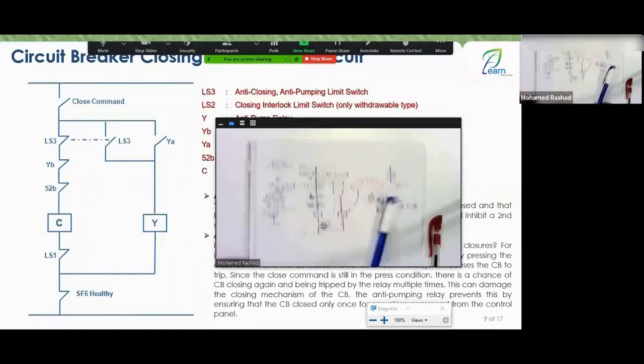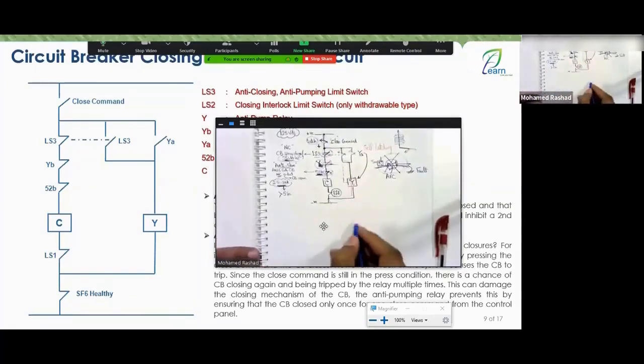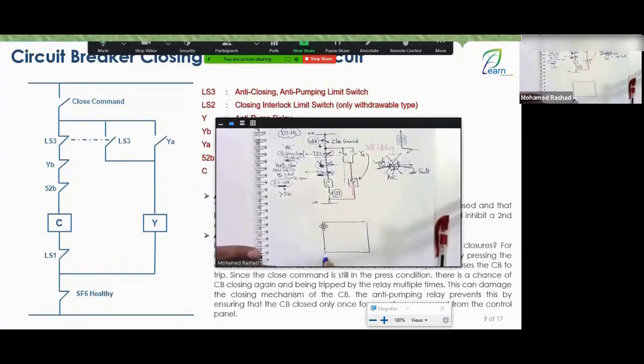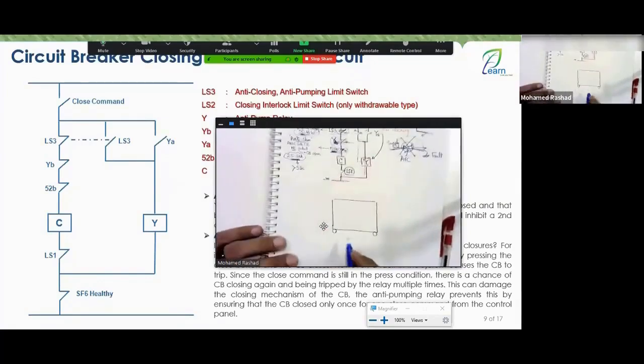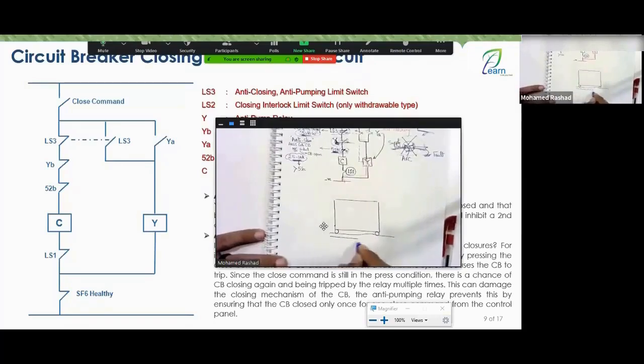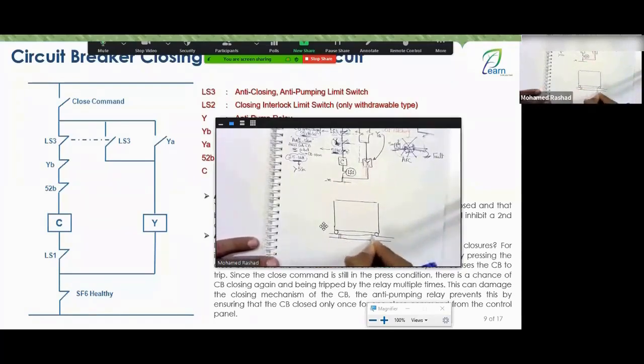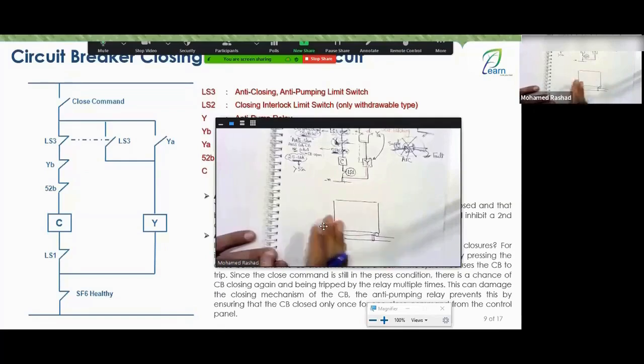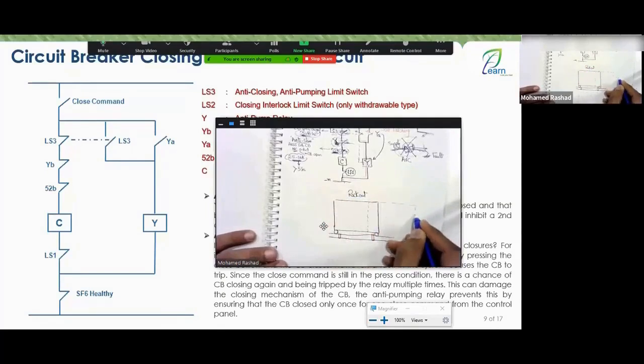If I'm looking at the breaker from the side like this, here's the circuit breaker. It has wheels here and wheels here. I'm looking at it from the side, right? Okay, and this breaker moves along the track of the cell itself, right? Very good. Here, engineers, there is a hole. And here, there is a hole, exactly, a hole with an opening. A normal breaker, completely rack in or completely rack out. If it's completely rack out, it's like this. But if it's rack in, you'll find the breaker comes in like this. So you'll find this wheel came here, and this wheel, here it is in front of us, came here. Let's mark it in red like this, and in red like this, exactly.